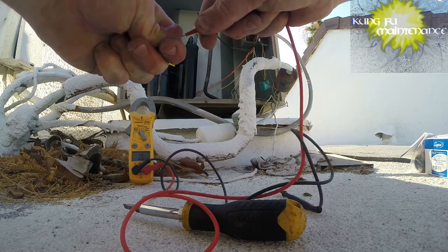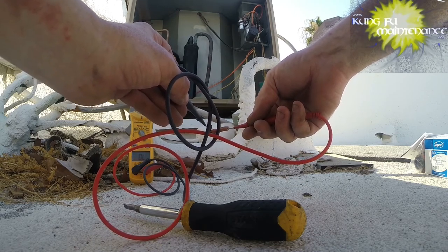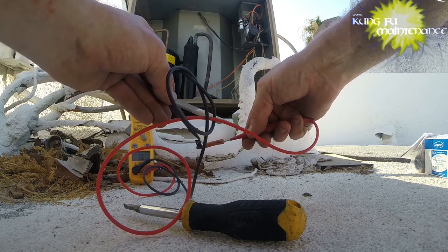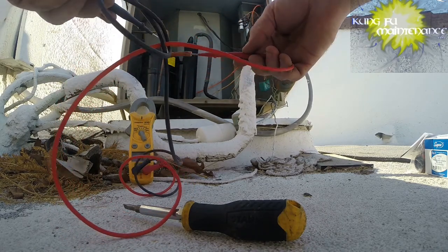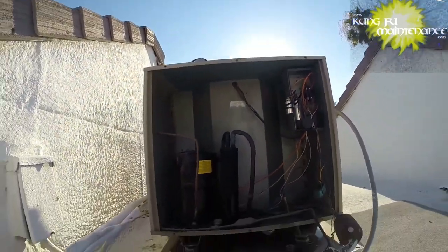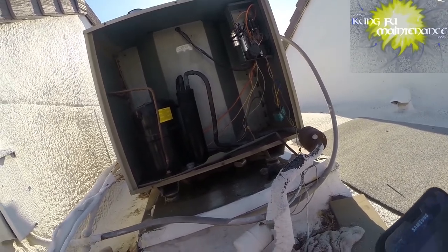I'm right into the wire on one side, and then here's the other side — nothing. But if I get closer it's kind of hit and miss — sometimes it's connecting, sometimes not. And that's why I was getting the intermittent start of the air conditioner. Strange one. Thanks for watching. Kung Fu Maintenance — we're back in the mix, back with a fix. It was 121 yesterday, supposed to be 121 today. It's 117 right now and it's 5:55 p.m. Thanks for watching.